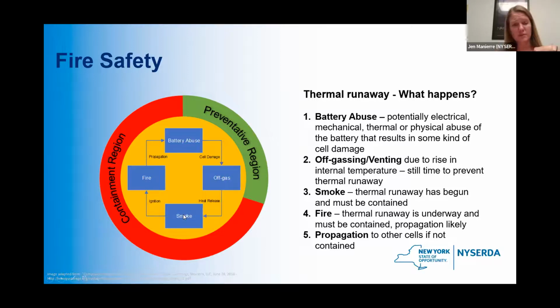If it goes unchecked for too long, you might start seeing smoke. And if that goes unchecked for too long, it might actually ignite and catch fire. And if it's catching fire, just like the heat from one cell might spread to the next, the fire can spread from one rack of batteries, perhaps to a rack of batteries that's next to it. And that's propagation going down the line if it's not contained. So this is what happens if we don't have any checks and balances in place, right?